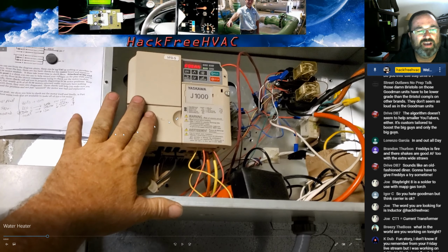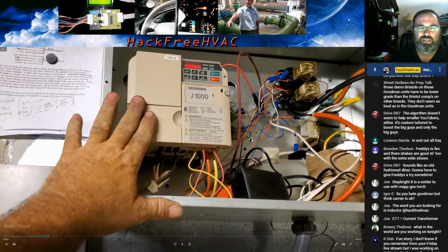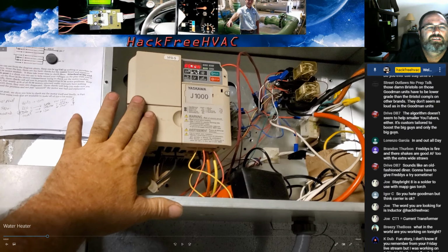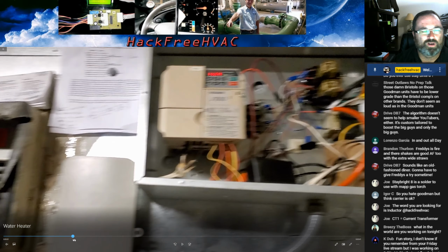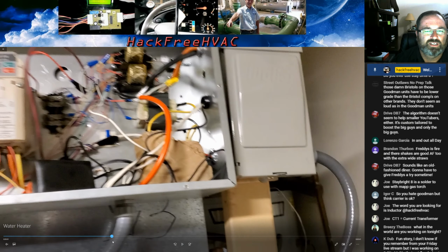I've had this VFD running for 3 or 4 months at least before summer started. There's just a couple relays on my homemade controller - one brings it in and turns it on, and another for high speed and low speed. It runs at 40 hertz until the leaving water temperature goes over 130, then it drops to 35 hertz. On the side I have my water heater and a circulating pump.